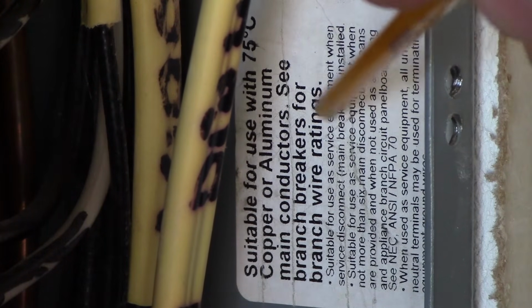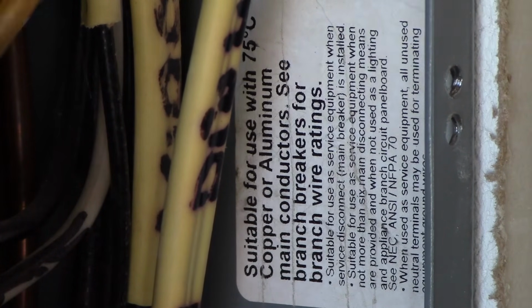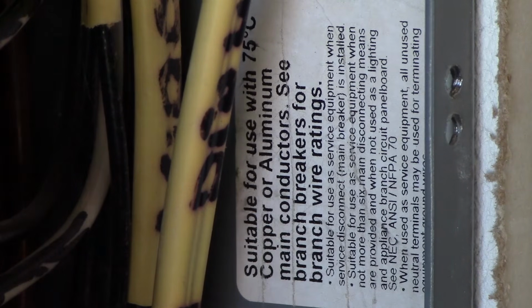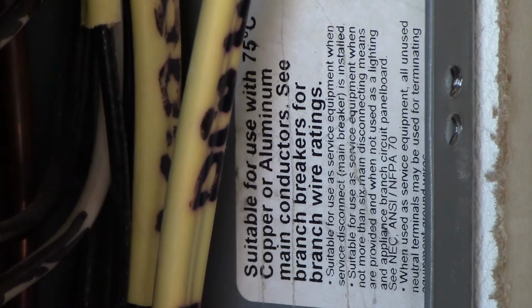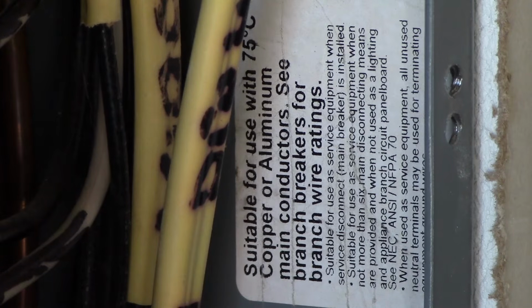Again, the terminals on these branch circuits are going to be rated here at 75 degrees C. Most all circuit breakers are. They might be 60/75 degrees C. None of these, generally, especially in a residential application, are ever going to be rated 90 degrees C. Again, we use 90 degrees for adjustment and corrections only.